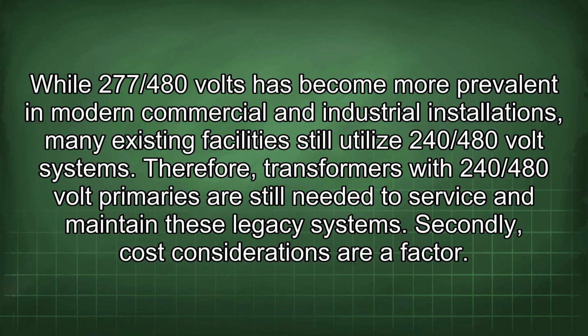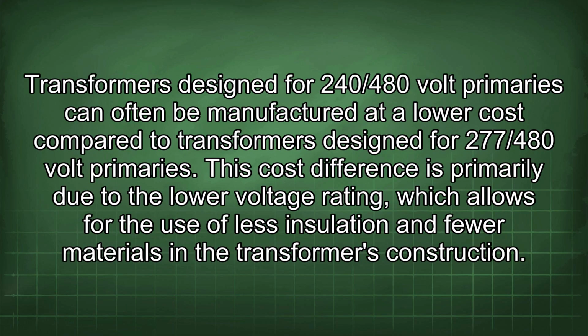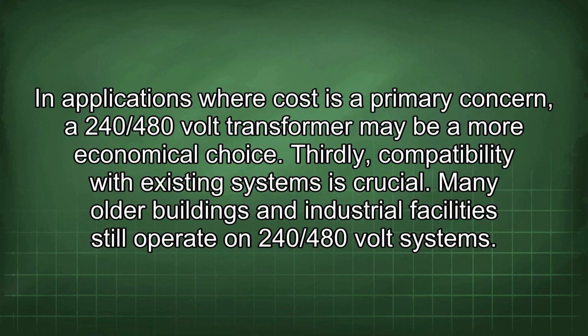Secondly, cost considerations are a factor. Transformers designed for 240/480 volt primaries can often be manufactured at a lower cost compared to transformers designed for 277/480 volt primaries. This cost difference is primarily due to the lower voltage rating, which allows for the use of less insulation and fewer materials in the transformer's construction. In applications where cost is a primary concern, a 240/480 volt transformer may be a more economical choice.